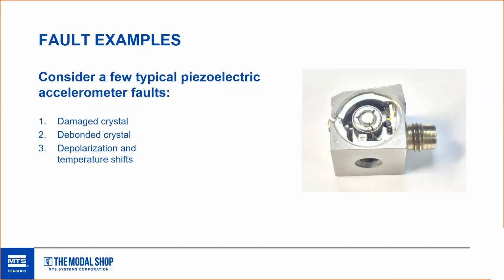Depolarization and temperature shifts. Depolarization of the sensing crystal can occur if the elements run at temperatures above the operating range, and it can result in scaling issues or complete fault of the sensor. Generally, piezoelectric elements are temperature sensitive even within their operating range, and scaling may occur. So check your specs and understand how it affects your test. And think about, would a handheld calibrator check this?